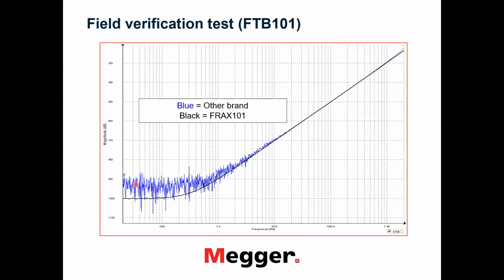Like, for example, here, this is not a transformer, this is a field verification test, which is also one of the good approaches before you start to measure with your system, to verify whether it is in working order. But here it is just an illustration that the FRAX can measure at this lower level of minus 100 dB quite well. And there is another brand, the blue one, where we have noise only here, and then the noise disappears somewhere about minus 65 decibels only. So this is very poor performance of some other SFRA instrument. This is not something I would recommend.